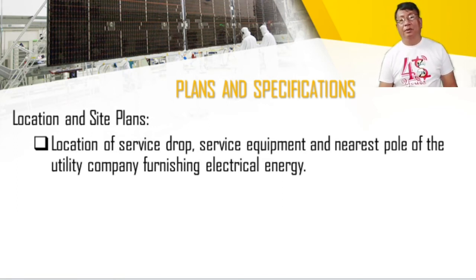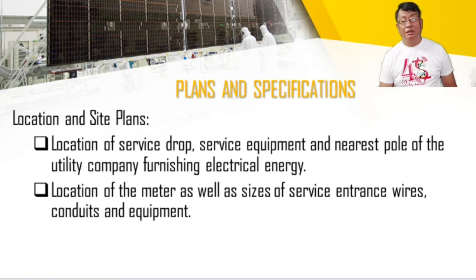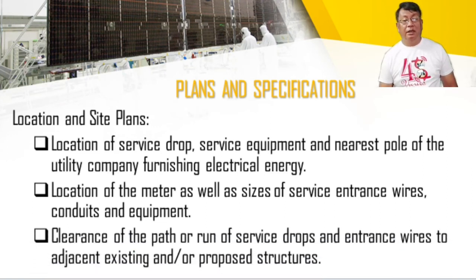Okay, so you have to indicate, no? You have to indicate the nearest pole where your power supply will be connected to. Then the location of the meter, as well as the sizes of the service entrance wires, conduits, and equipment. Okay, so the location of the electrical meter, no, or electric meter. Then the clearance of the path or run of service drops and entrance wires to adjacent existing and/or proposed structures. Okay, so clearances, distances between devices and service entrance and any other path, no? So we have to specify that.